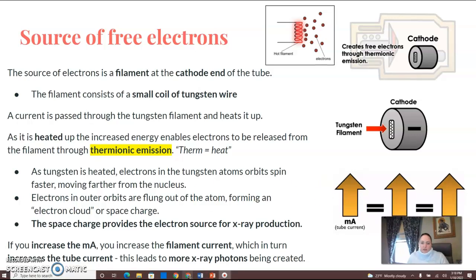The source of free electrons is a filament at the cathode end of the tube. Remember, the cathode end is the negative end. The filament consists of a small coil of tungsten wire. Current is passed through the filament and heats it up. As it's heated, the energy increases and electrons are released.